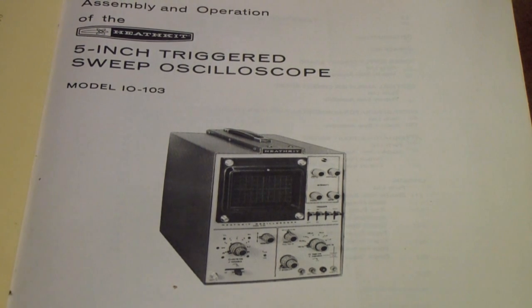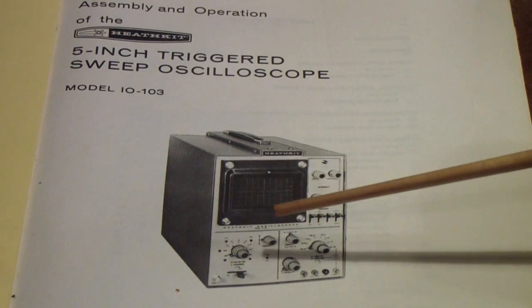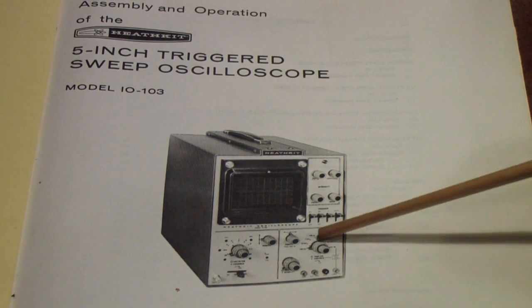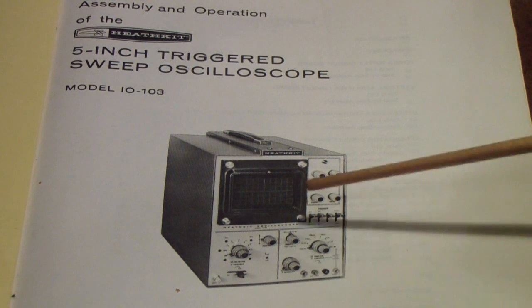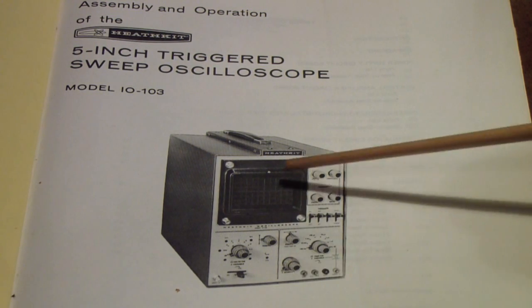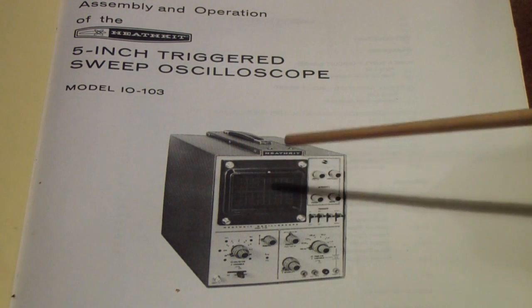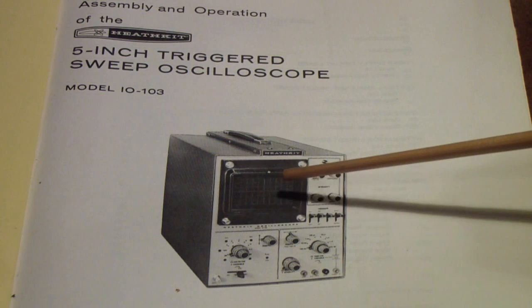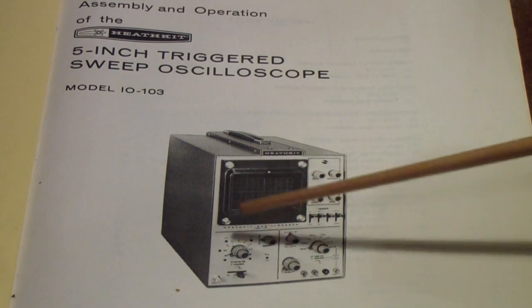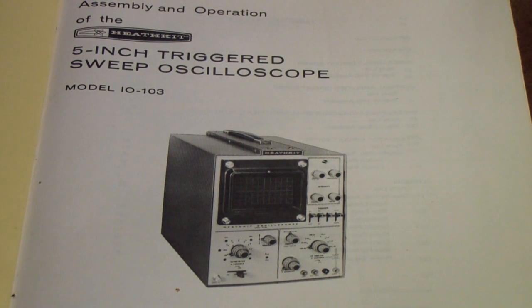But before we get to that, let's look a little bit at what calibration entailed in this. In a modern digital oscilloscope, the signal that is often brought out for, that I inadvertently call the calibration signal, is actually only intended to compensate the probes. We'll look at that a little later, too. But I thought it might help to clarify, in the old days, the analog scopes actually had to be calibrated, and it wasn't just a one-time process. You had to do it pretty regularly.